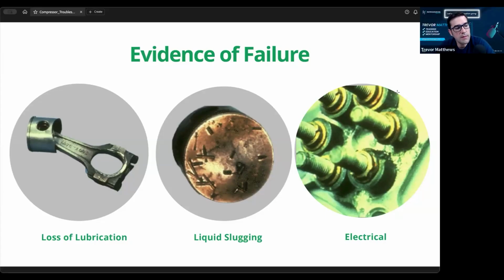Yeah. I don't recommend it myself. I never use Acid Away. I always put a suction line filter dryer on and then remove it if the pressure differential gets over what the manufacturer recommends. Because they say it right in there. You go into Sporlan, you'll go into the Copeland ones, and they'll say, depending if it's a permanent installation or just a temporary installation, they'll tell you the times on when to pull it out, after 24, 48, 72 hours. But this is something that you need to check.